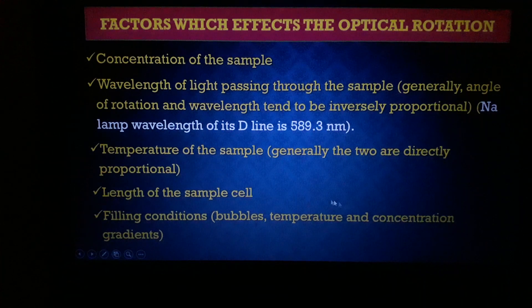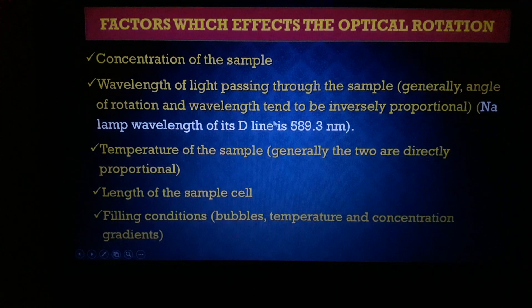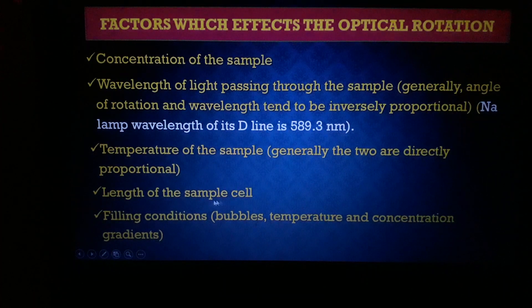There should be no bubbles and no color; it must be a clear solution when filling the sample tube. When performing analysis, keep in mind: prepare and dilute the sample as per the monograph, use the wavelength specified in the monograph, control the temperature, use the correct cell length, and follow proper filling conditions. These factors are very important when performing optical rotation or specific optical rotation testing.